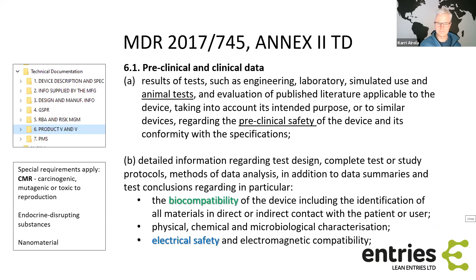So here at the launch, and especially when you are collecting the technical documentation, in the first place it could be that you are happy with the result, and it's according to the standard. But then you should consider how this data is evaluated and assessed by notified body experts when they are assessing all points of view of your medical device. So it's probably a good idea to have a short break and stop for a moment when designing these tests, especially if you are working with high risk devices.